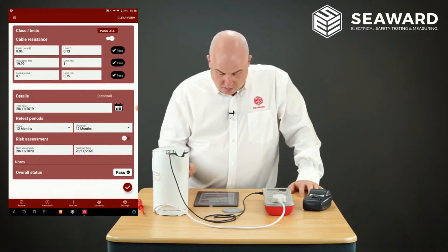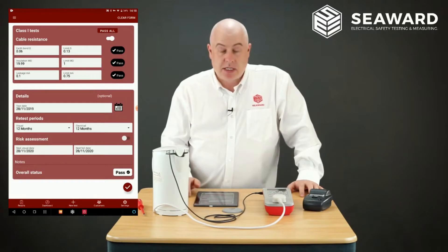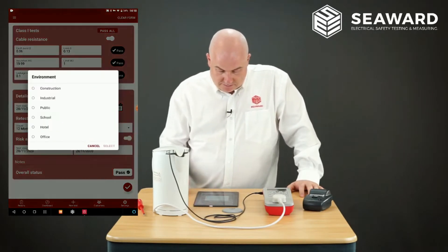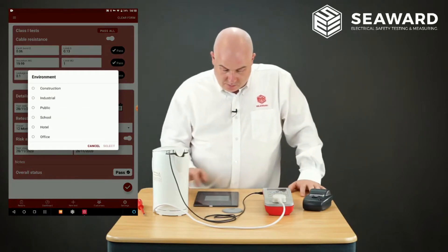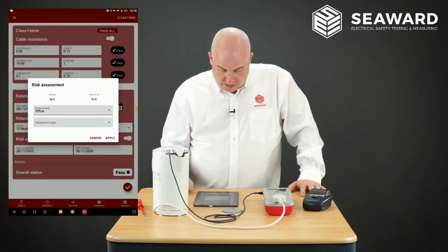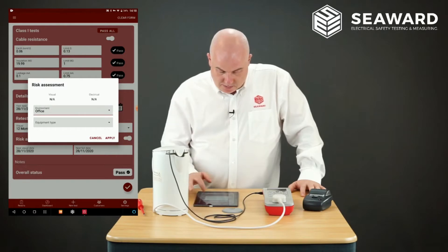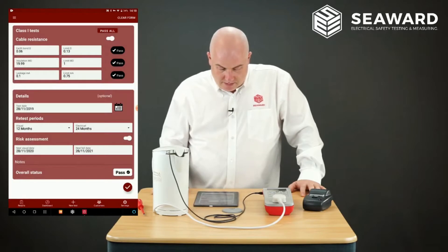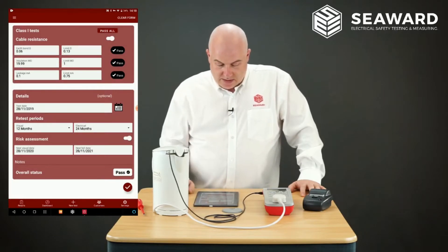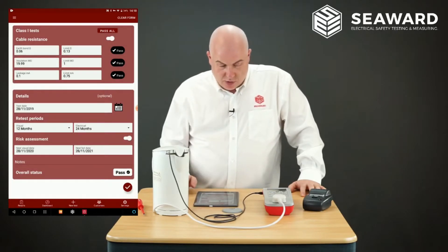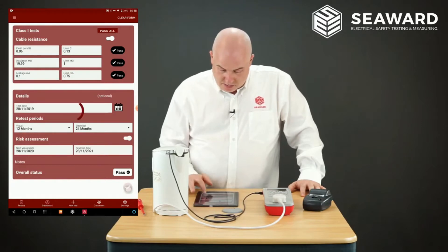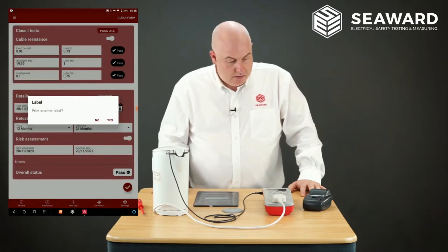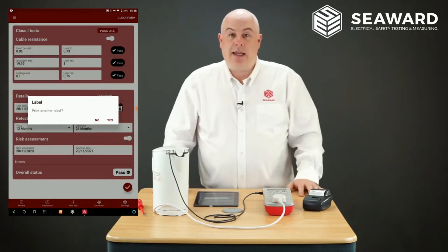I can then carry out a risk assessment. I tick the risk assessment calculator and select the environment — in this case Office — and the equipment type, which is Handheld. I press Apply and this works out the retest dates for us. I can put a comment in if needed, then tick that. It then asks: do I want to print a label? Yes I do — and out comes my PAT label.